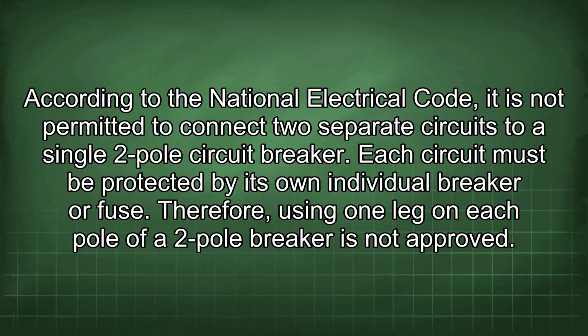According to the National Electrical Code, it is not permitted to connect two separate circuits to a single two-pole circuit breaker. Each circuit must be protected by its own individual breaker or fuse. Therefore, using one leg on each pole of a two-pole breaker is not approved.